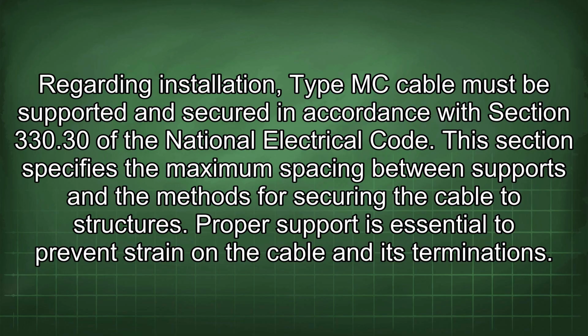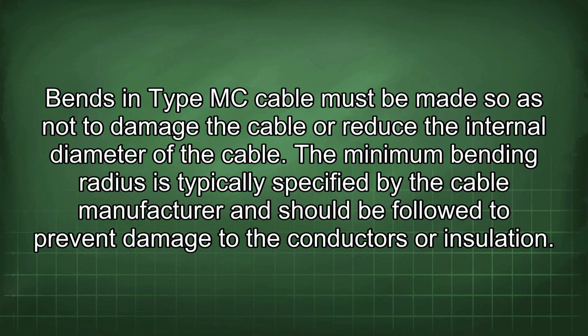Regarding installation, Type MC cable must be supported and secured in accordance with Section 330.30 of the National Electrical Code. This section specifies the maximum spacing between supports and the methods for securing the cable to structures. Proper support is essential to prevent strain on the cable and its terminations. Bends in Type MC cable must be made so as not to damage the cable or reduce the internal diameter of the cable. The minimum bending radius is typically specified by the cable manufacturer and should be followed to prevent damage to the conductors or insulation.